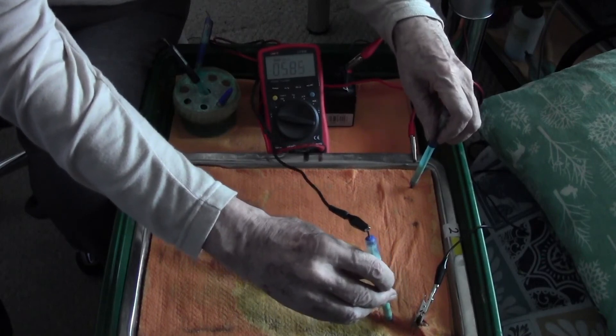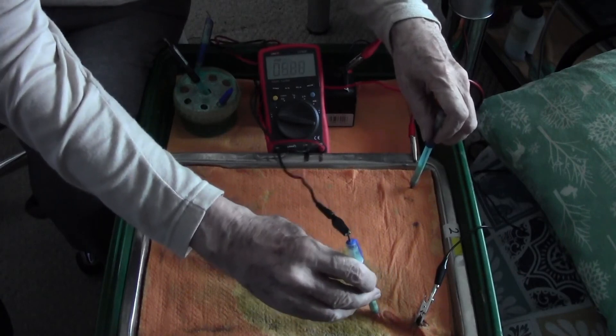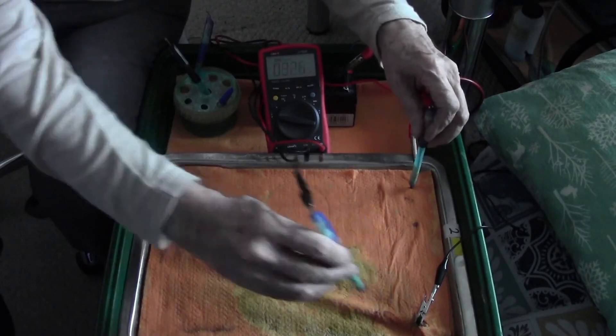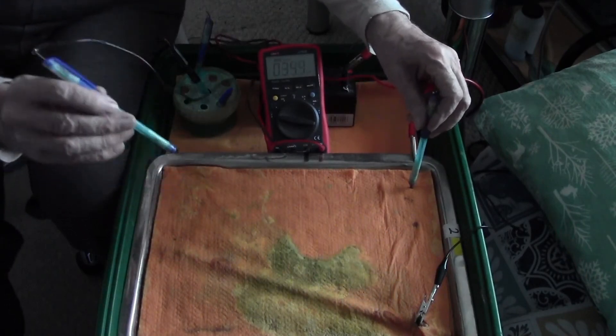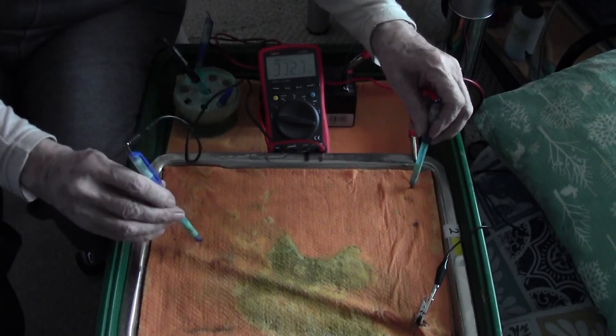so we have a situation where by stepping one of these copper copper sulphate electrodes over the ground over the top of the pipeline we can find the voltage.